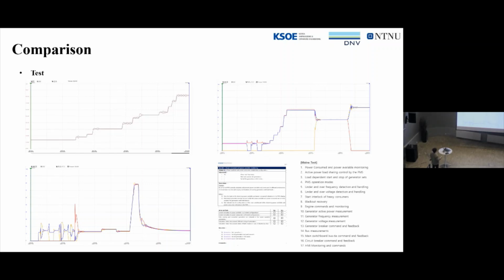And in this one, we tried to connect and disconnect generators one by one. Then PMS tried to control the generators, like disconnecting one, then reducing load from that generator and adding more load to another generator like this. After connecting two of the generators, PMS still tried to keep the load sharing mode symmetrical.